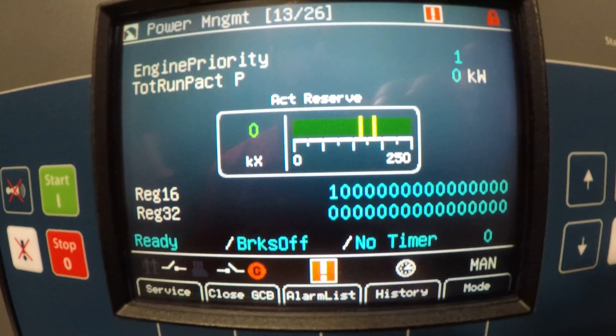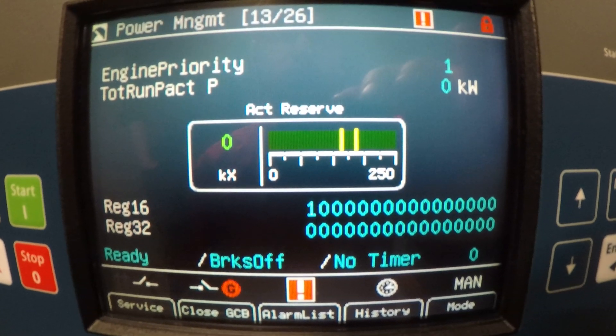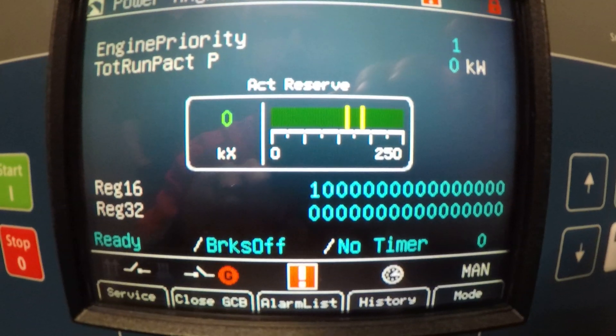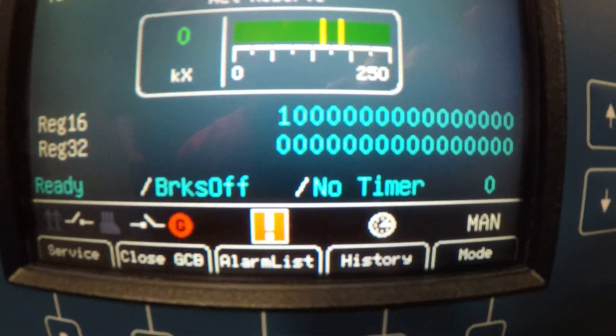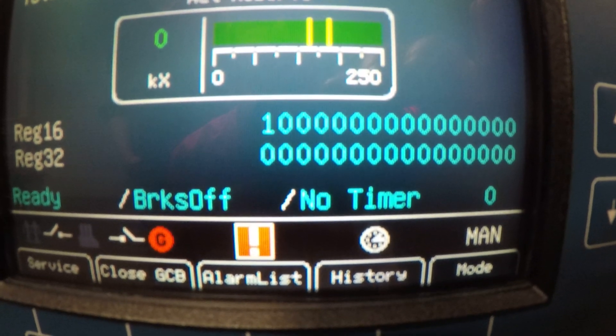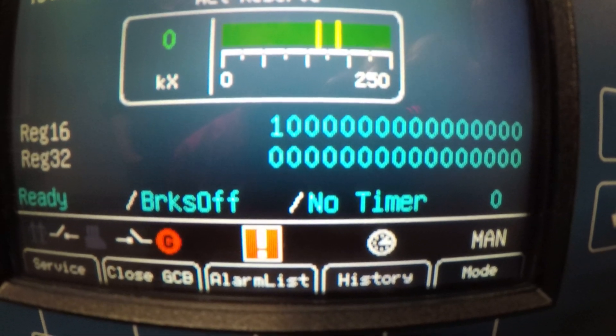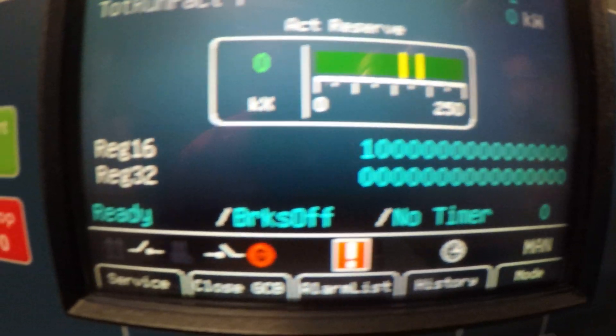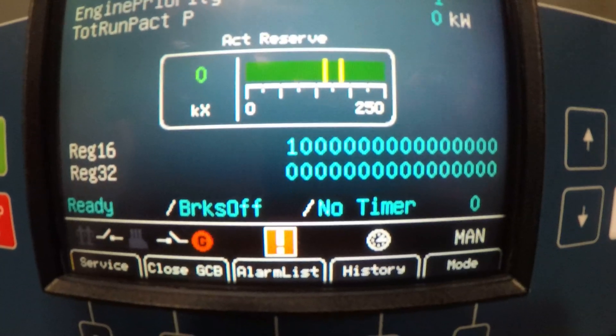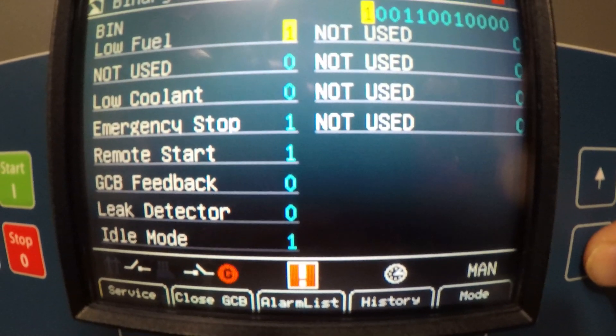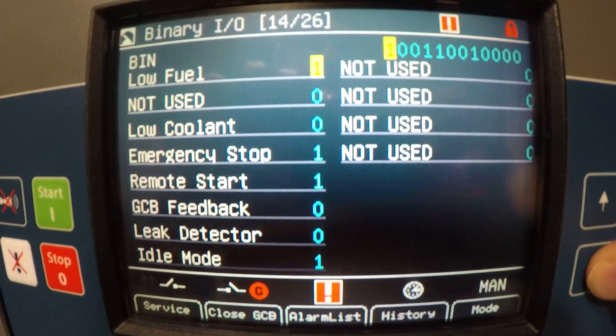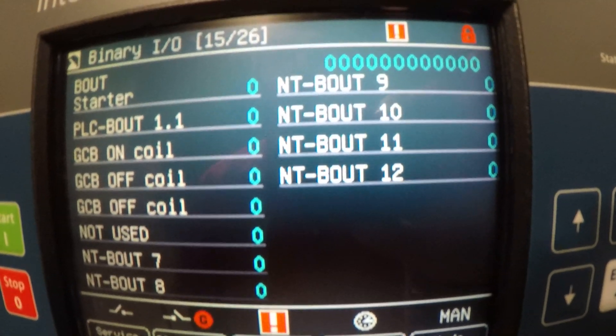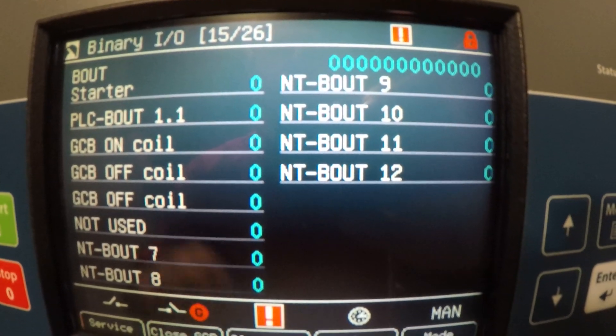Power management screen is dealing with your parallel set points. In the middle there, active reserve is going to be your capacity of that parallel set. You have a binary code of ones and zeros — the top line is going to be your genset, the bottom zero is when the circuit breaker closes. These are all sets from 1 to 32 different sets onto this parallel genset. You got binary inputs and binary outputs such as starters, on-coils for parallel, and your motorized breaker control.